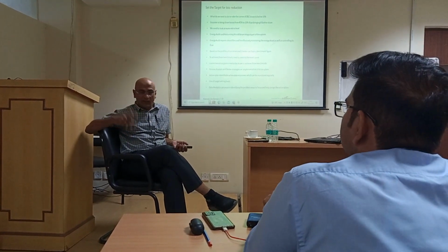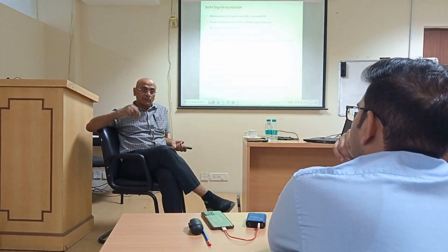The meter might not be working, the meter might be slow, or the meter tampered. There are so many other things, like metering not done. You will find out this problem, and you may not have a meter immediately with you. You find the meter is not working, so you report that, and then the billing happens as an average. But you have to replace the meter. So that is the action plan.